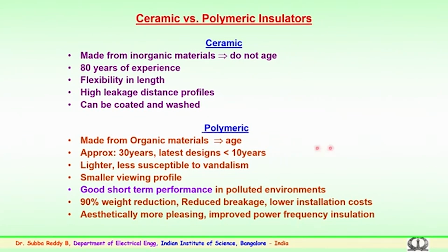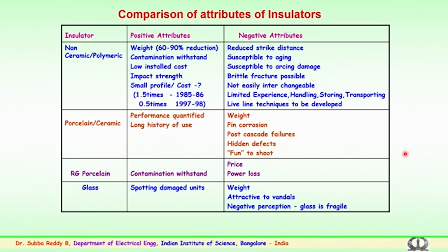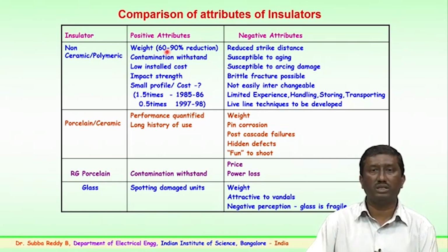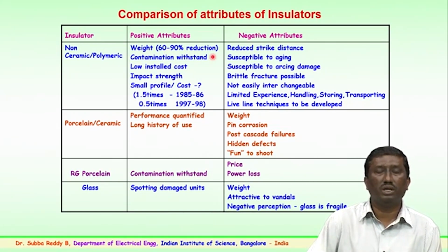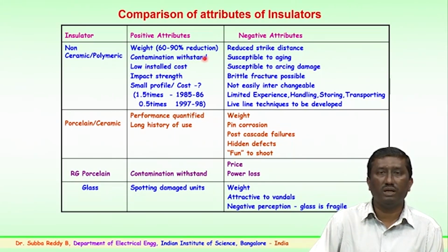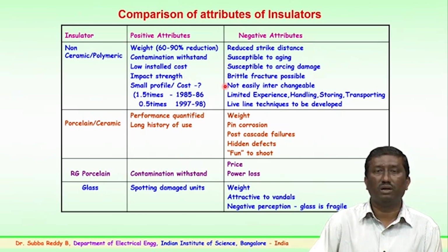So, this gives you the comparison of attributes for the different insulators which have been used for transmission over a period of time. For the non-ceramic, polymer or composite insulator, these are the positive attributes and these are the negative. As mentioned earlier, the weight reduction is anywhere between 60 to 90% depending upon the voltage level and the hardware being employed. Contamination withstand is much better compared to ceramic, there is low installation cost, better impact strength and a small profile, and also cost gets decreased. This is very important.